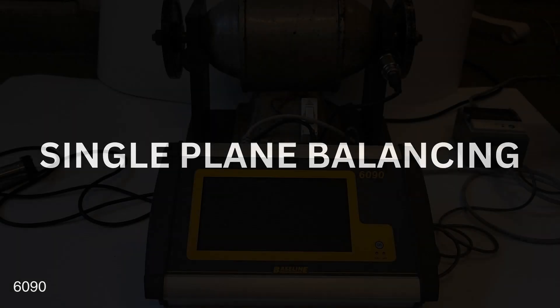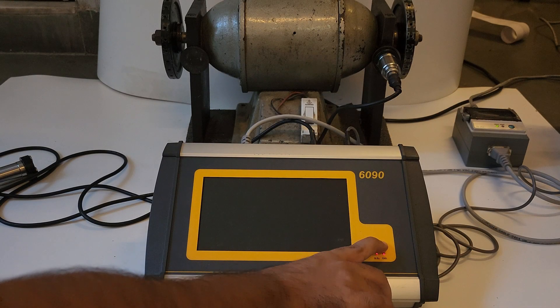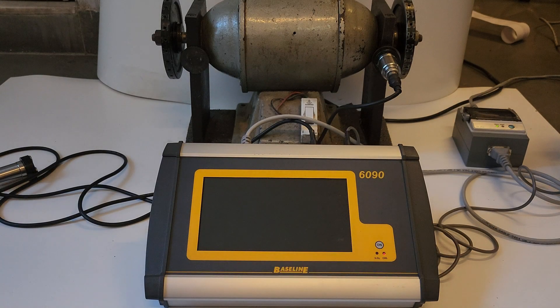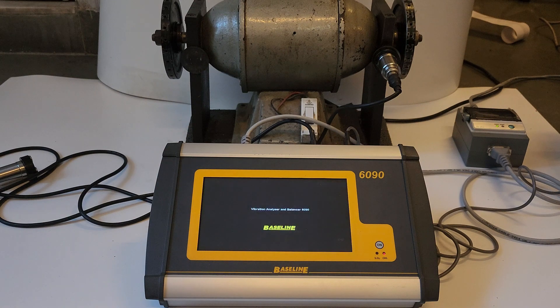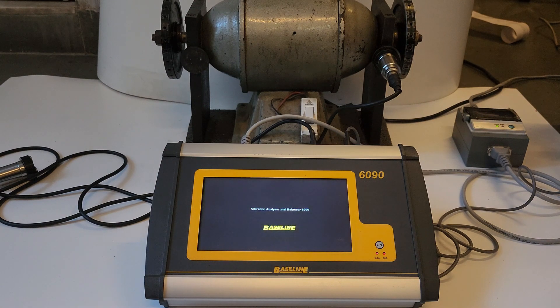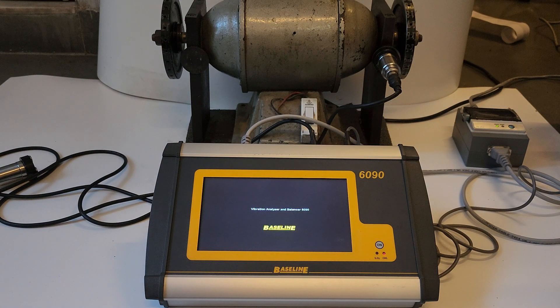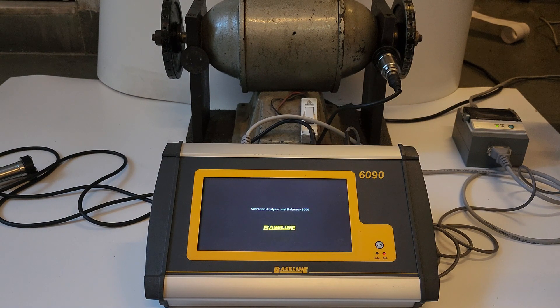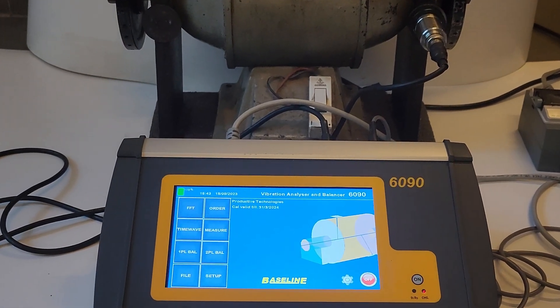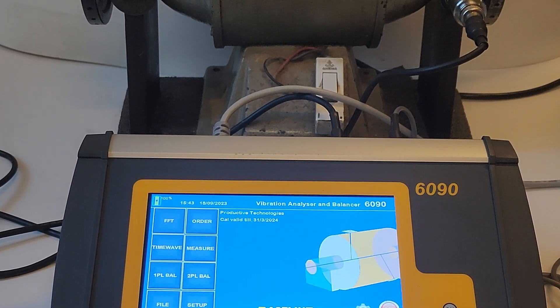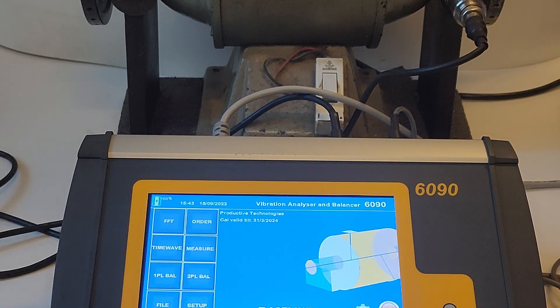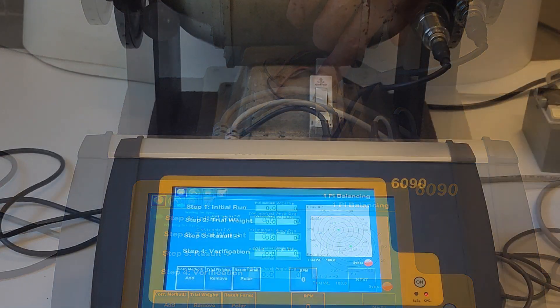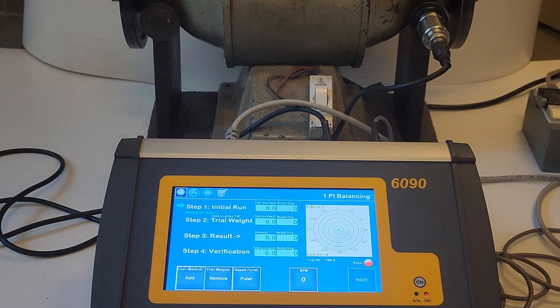Two-plane and single-plane dynamic balancing can be performed in situ with the 6090. It has all the required vector calculation algorithms built into its program. Thus, the operator is freed from the task of determining the weights by calculations or hit and trial methods resulting in vastly improved quick and accurate results. For single-plane balancing, select one plane from the home screen and then follow the instructions on the display.